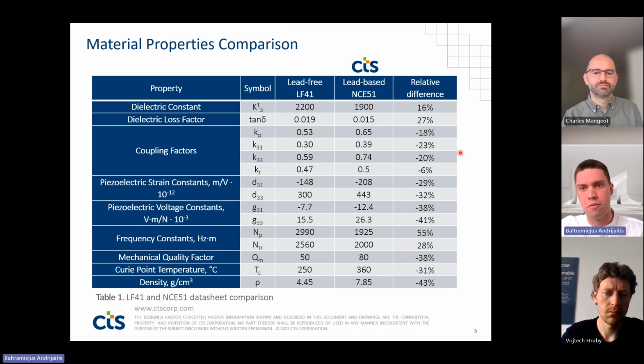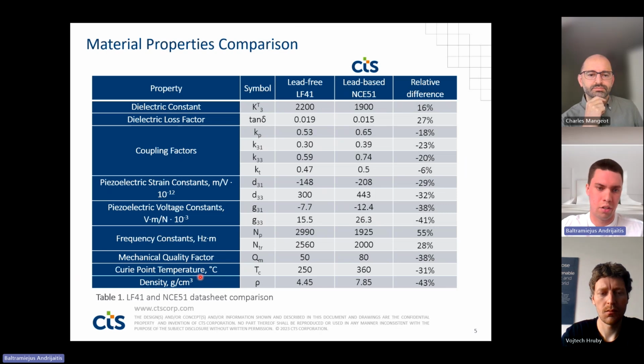As you can see from the relative differences of each property, unfortunately, lead-free material seems to be weaker in the application. However, there are a few advantages, like the dielectric constant, which is higher. That indicates that in the final application, the capacitance of the time-of-flight transducer could be higher. Another advantage could be density. Because of the lower density, a lower acoustical impedance should be acquired, which means better element matching with the fluids, which is required in this application case, and just better effectiveness of energy transfer. So later we will see if it's enough to match the PZT material in performance or not.